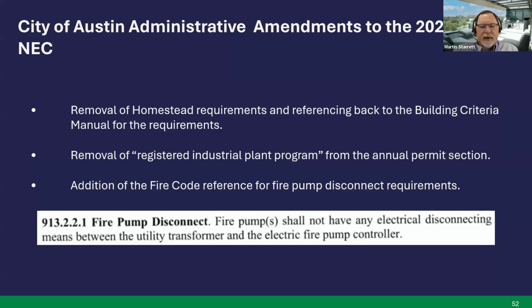We also added a fire code reference concerning the fire pump disconnect requirements. In the City of Austin Fire Code, you're not allowed to have a disconnect between the fire pump and the fire pump controller. You're allowed to by the National Electric Code, but here in the city, you cannot install one. Next slide.